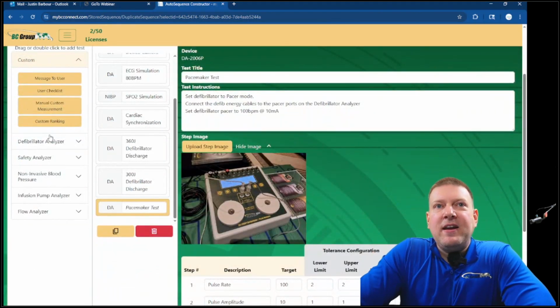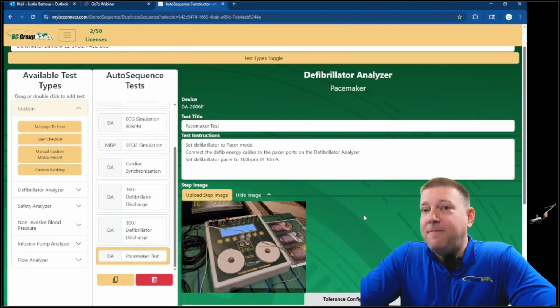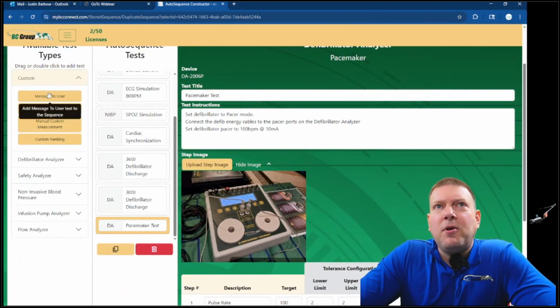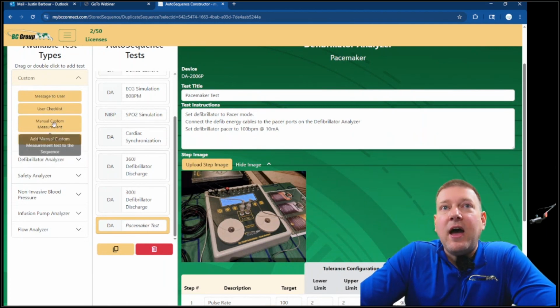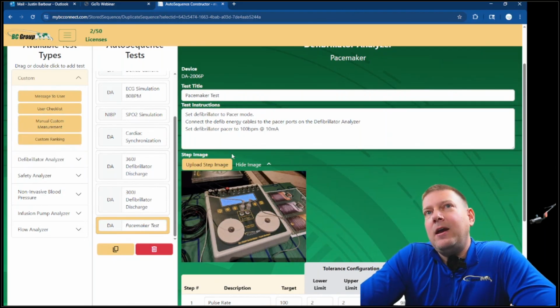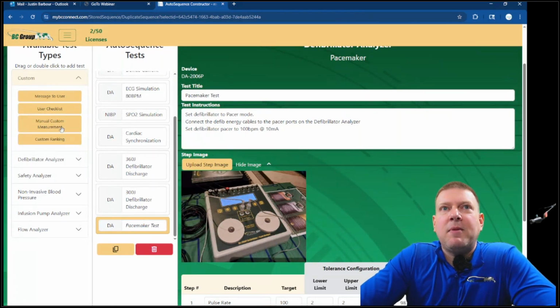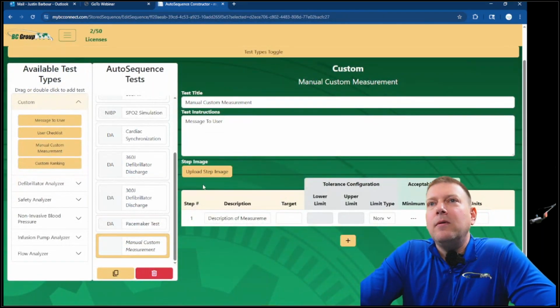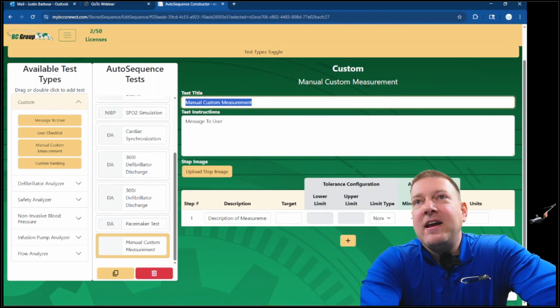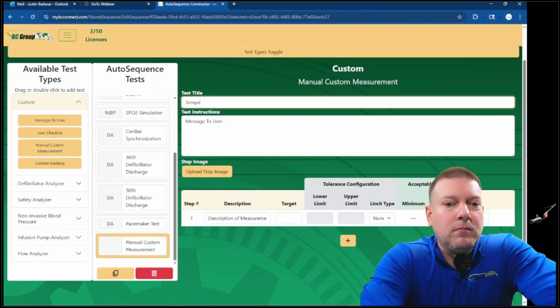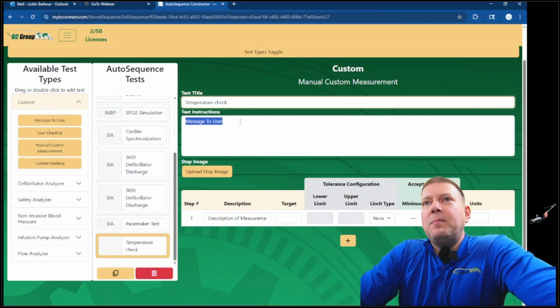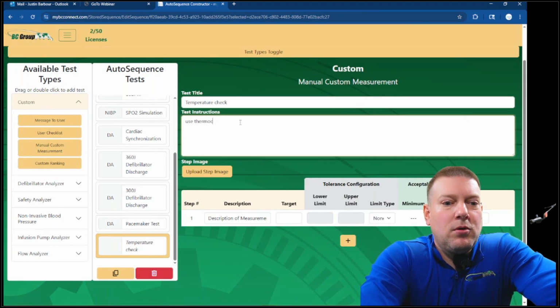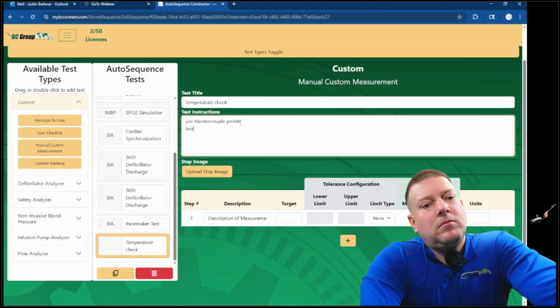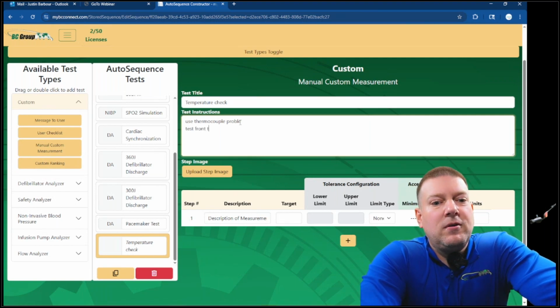So guys, that is a quick overview of a defib auto sequence. I'll show you a couple other things that we can add, some cool stuff. We can do a checklist. I can do a manual custom measurement. So let's say I have a thermal cabinet, and on my thermal cabinet, I want to add a temperature. Just for sake's sake, we're going to add a temperature measurement to a defibrillator here. So we're going to do a temperature check. Use thermocouple probe. And next one, let's test front, top, and lower rear of cabinet.